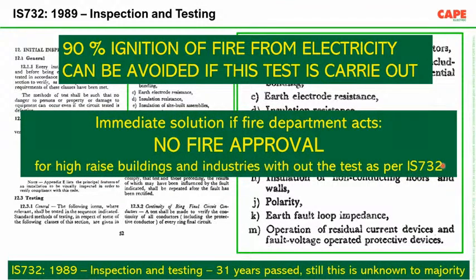So the fire department, because in case of fire the most affected people are the fire and rescue department of the state governments, they can make an immediate solution. If the fire and rescue department make a regulation or a rule saying that we will not give you fire approval if this test is not carried out, so simply make a circular and ensure that every installation, especially the large ones like high-rise buildings and industries, is tested as per this IS 732, then 90% of ignition of fire from short circuit can be avoided.